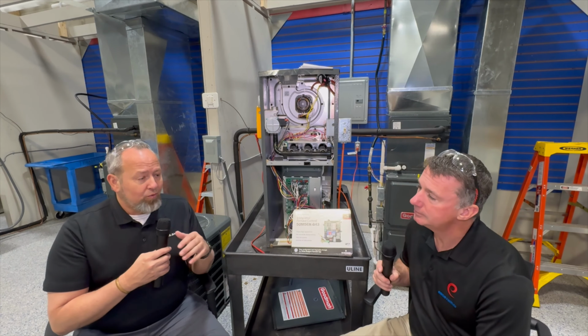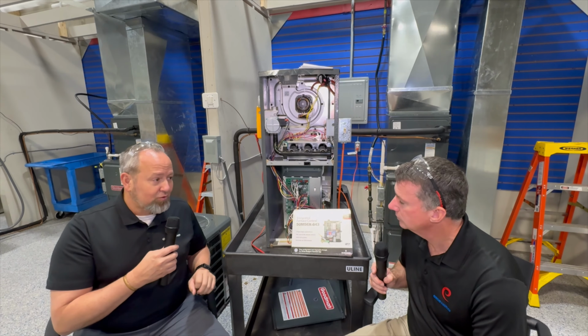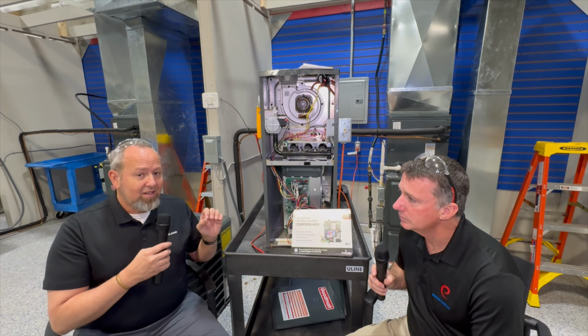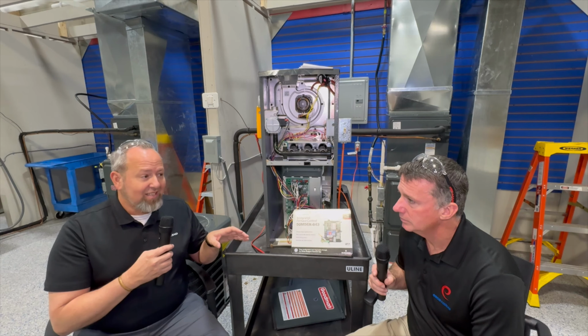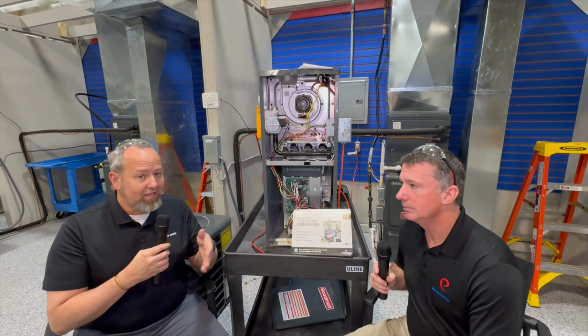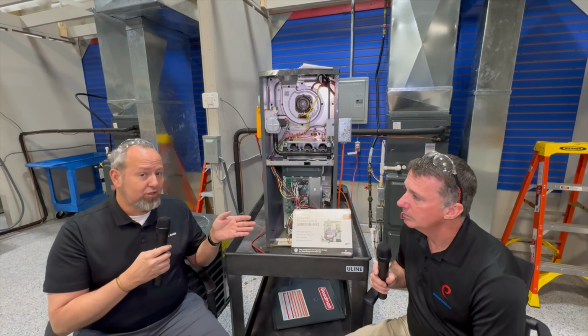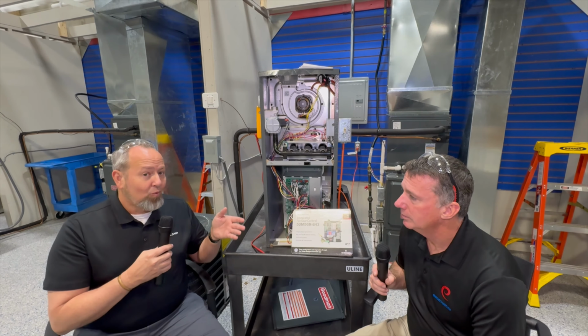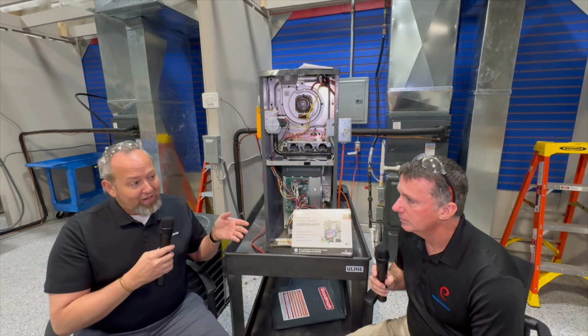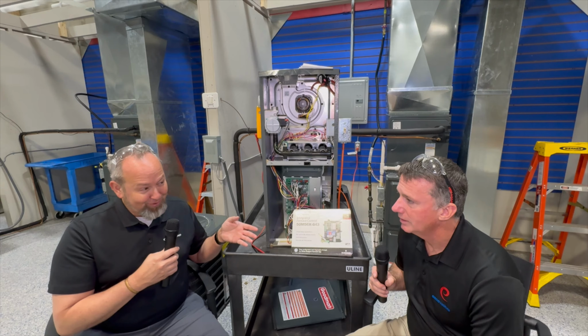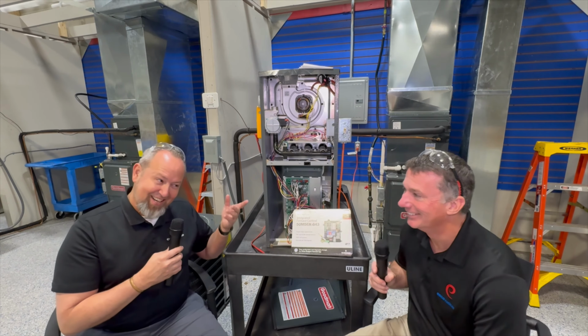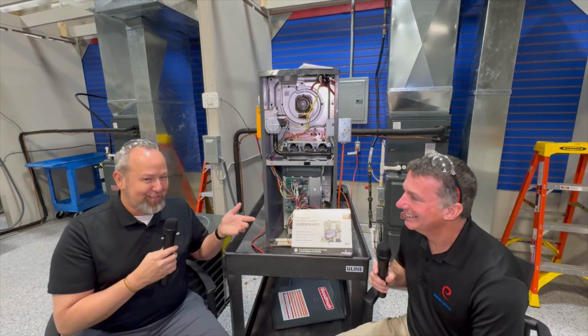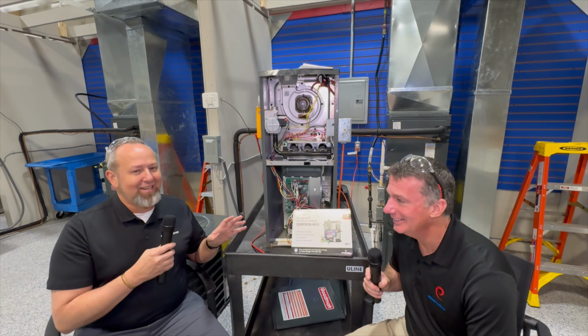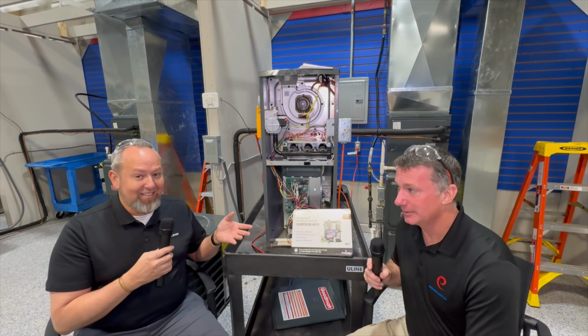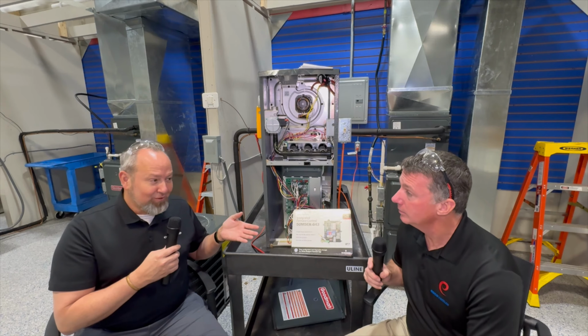So when we designed the 50M56X, we designed it with the idea that we were going to send out that DC signal for all ECMXs, and it would work across the board with all of them. Now, it works great. The problem is, if you're a technician used to 24-volt AC and that's all that's been trained up to this point, then it's like, whoa, wait a minute, I got a bad new board because it's not sending that 24-volt signal out.